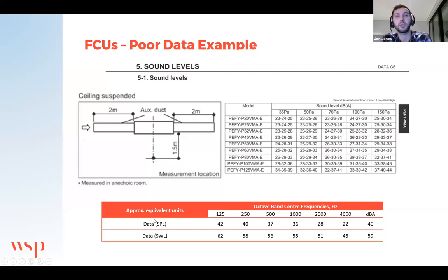Just looking at the bottom here, and I suppose to labour the difference in terms of dBs again, here we've got an octave band spectrum, which is the frequency noise data from 125 to 4 kilohertz. But just looking at the broadband level, which is dBA, A weighted. I won't touch on that too much today, but it's to do with the sensitivity of human hearing and how these broadband levels are perceived. But for an equivalent unit here, we've got a sound pressure level of 40 and a sound power level of 59. So it hits home the importance of understanding what noise data you have and the conditions it was measured in and what it's presenting, because if you take one to be the other, you could be significantly out with any predictions.